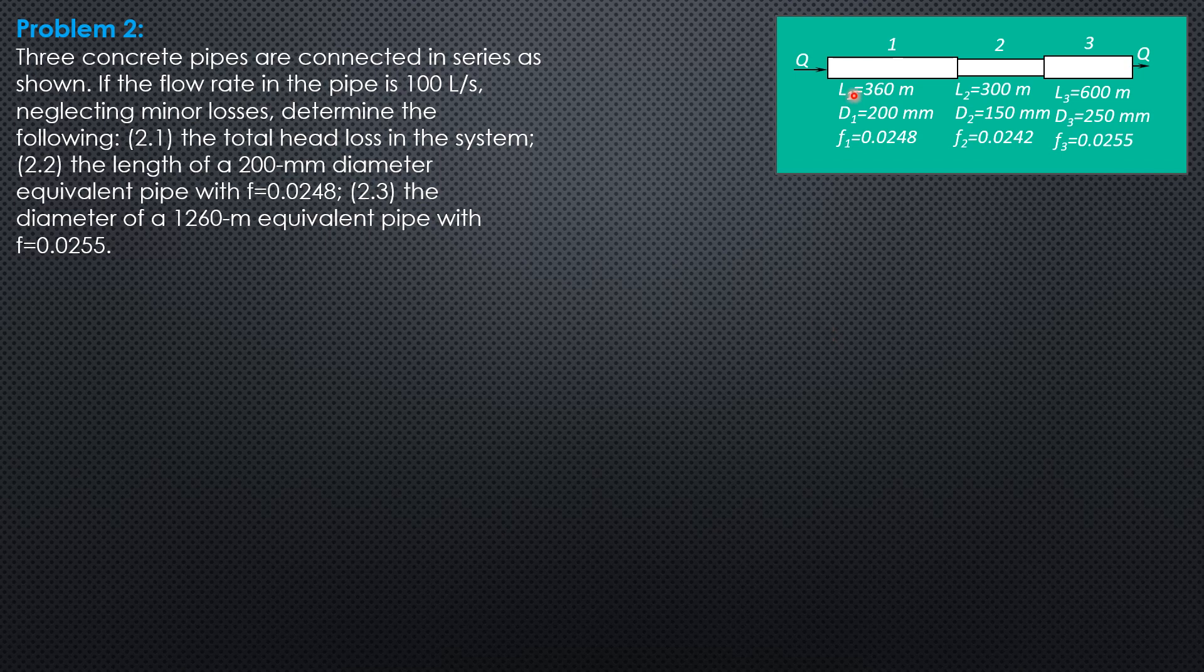So the total head loss is again the sum of the individual losses. And the formula by Darcy Weisbach is, head loss is 0.08, summation of 0.0826 friction factor length discharge square over diameter to the fifth.